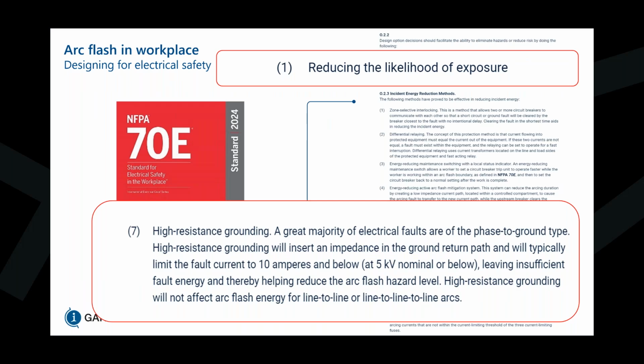The only blind spot for high resistance grounding is that in the case of a line-to-line or a line-to-line-to-line failure, the resistor at the source that's connected between neutral and ground is no longer in the path of the ground fault. So if I have 2 feeders, for example, feeder 1 phase A faulted and feeder 2 phase B faulted, the 2 faults will circulate to ground and circulate between each other and grow to thousands of amps. The NGR will not see any of that current, and that's why phase-to-phase and 3-phase failures are not seen by an HRG system or impacted by it.